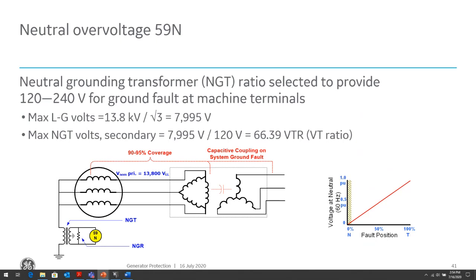But it gives us significant coverage, up to 90% most of the time, of the winding. Now, the 59N, usually we have two stages of 59. We have a fast 59N and a slow 59N. And why we have that is, even though the delta-Y transformer provides isolation, there is capacitive coupling across the windings of the transformer, which can allow a little bit of ground fault current to get across the winding. And hence, for system ground faults, we will see a little bit of neutral overvoltage.